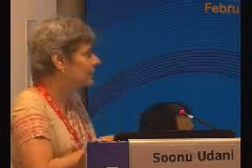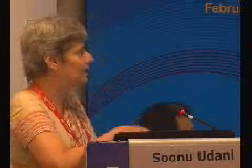Just one word on volume support. It is not like pressure support. It is more like PRVC. Because here what happens is the same way as in PRVC, a test breath is given, then the pressure is increased slowly till a target volume is achieved. And in the same way as PRVC, the target volume is achieved by increasing the pressure. And when there's an apnea pause and the ventilator doesn't detect a breath, it reverts to a PRVC mode. So volume support is not like pressure support. It is much more like a PRVC mode.